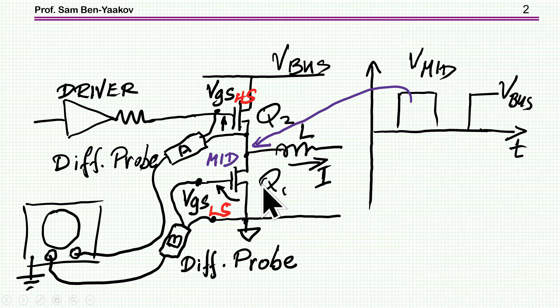Now the probes were switched: the low side is now probe B, and the high side is probe A. Let's look at the low side. With probe A we see this waveform, this oscillation here. With probe B there's very little oscillation, quite damped, but there's no question this is much cleaner than the other. Now for the high side: here is the high side with probe B, and here is the high side with probe A. Again, probe B is much cleaner, with no oscillations like those shown with probe A.